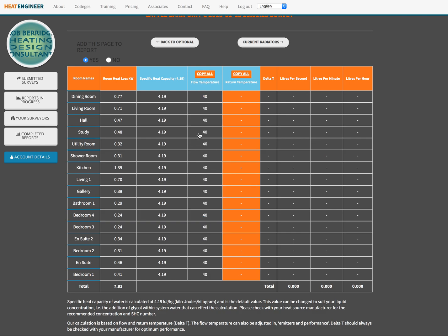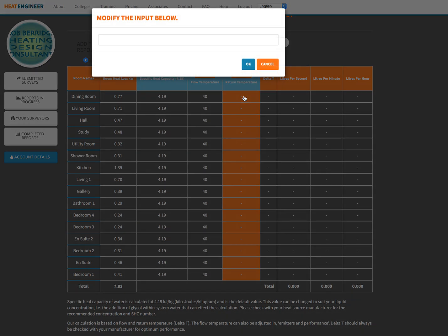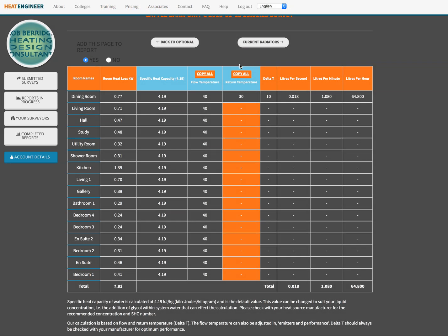Yep, so we're all populated now at 40 degree temperature. Now we've got to do our return temperature. Generally with heat pumps they will have a much much higher flow rate because the delta T, the temperature difference, the difference of temperature between the flow and the return is squeezed quite a lot. So just for this example you can change these numbers to any number that you want to, but just for this particular we will actually just have this return temperature coming back at 30 for argument's sake, giving you a temperature difference of 10.